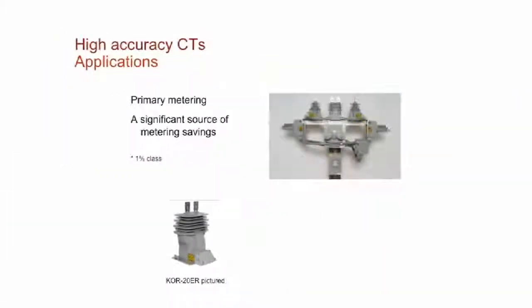But we also have primary metering applications as well. We'll start to see some more significant savings here. Primary metering would be used at, I'll just use my factory as an example in Pinetops, North Carolina. Okay. We have 15 kV circuits. We meter right off of the primary electricity there. So we're doing it at much higher levels here. Typically, you'll see these in rack-mounted units outside as electricity comes in directly from the feeder into the installation. Meter would be down below, usually at eye level. And so you have those typically mounted in racks like that.